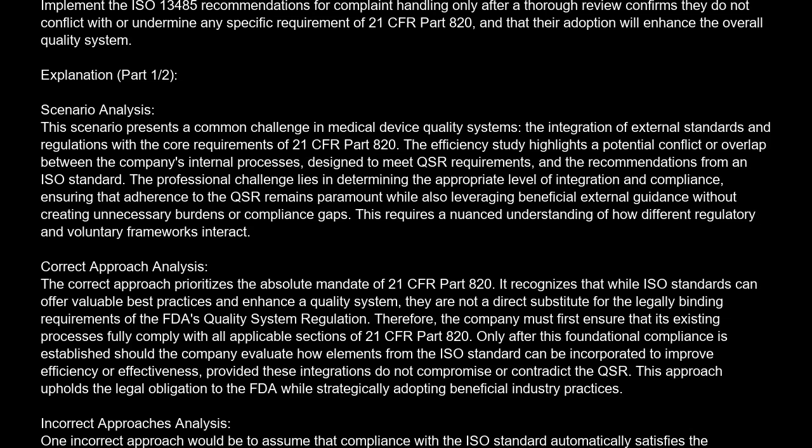The correct answer is B. Implement the ISO 13485 recommendations for complaint handling only after a thorough review confirms they do not conflict with or undermine any specific requirement of 21 CFR Part 820, and that their adoption will enhance the overall quality system.